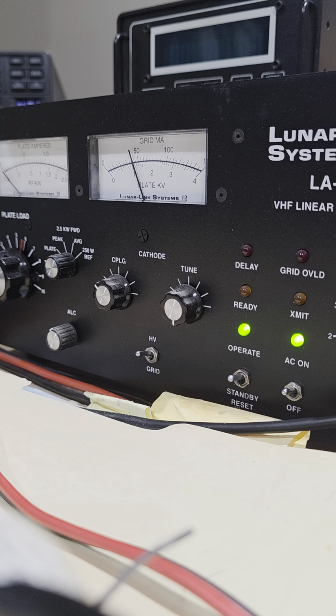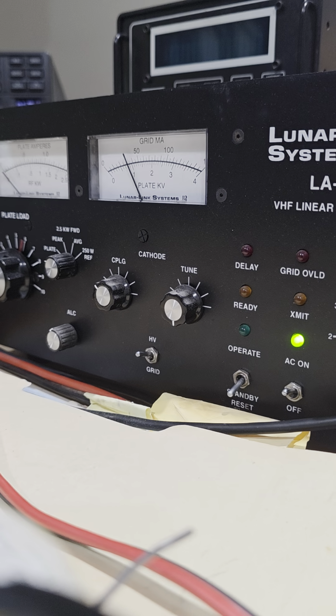So, and then if I do this, there's really no change. All that does is put 24 volts on pin 4 that goes down to the power supply and turns on the high voltage relay. So no change.